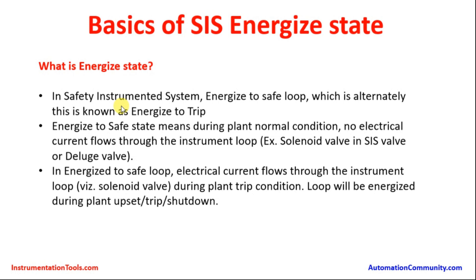In Safety Instrumented System, Energize to Safe Loop — which is alternately known as Energize to Trip — means that during plant normal conditions, no electrical current flows through the instrument loop. For example, a solenoid valve in an SIS valve or Deluge valve: under the plant normal operating condition, no current flows through the solenoid valve.